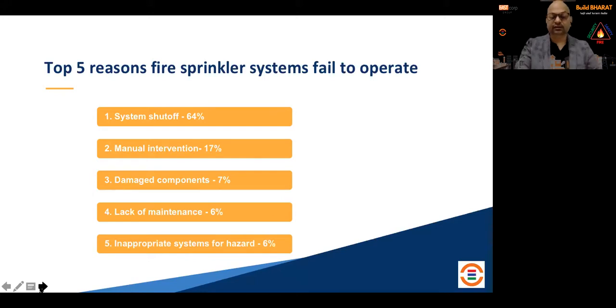Because you haven't identified the hazard correctly, you haven't identified the occupancy correctly—there's a change, but the sprinkler remains the same. I have seen, in fact, one of the warehouses where there was a 3-basement, 40-foot ceiling warehouse where K80 normal sprinklers were installed. When I investigated further, I found that the fire consultant who designed the system using K80 didn't have visibility of the 40-foot ceiling. He had been given an indication that okay, there will be some operation there, but nobody knew what operation would come, so they said go ahead and do it.